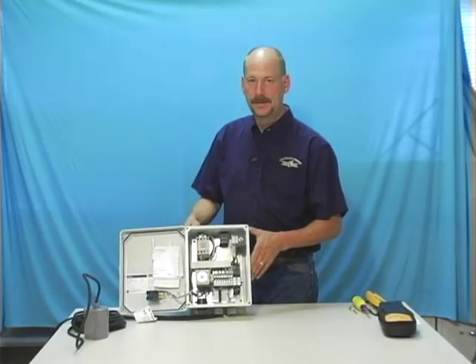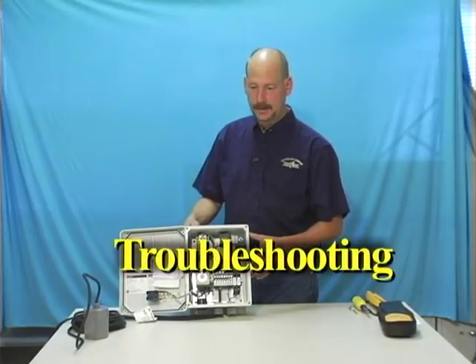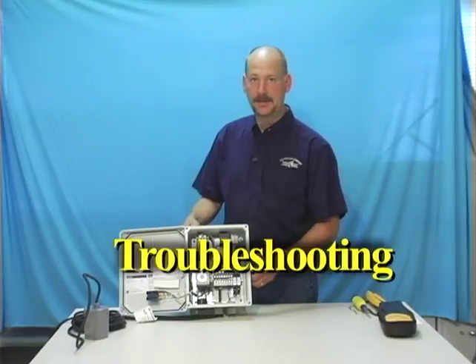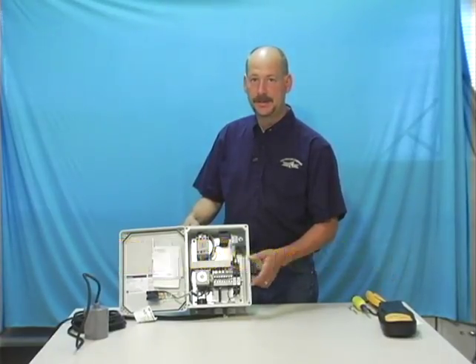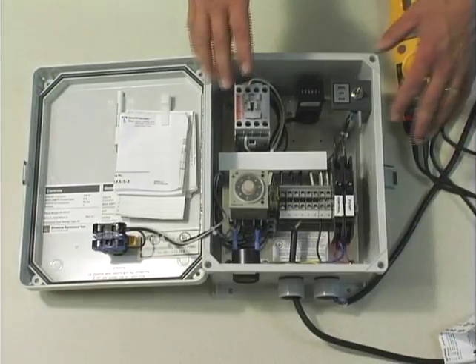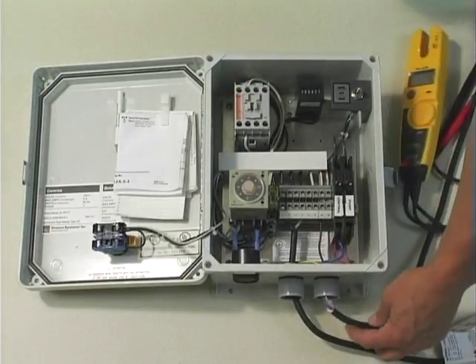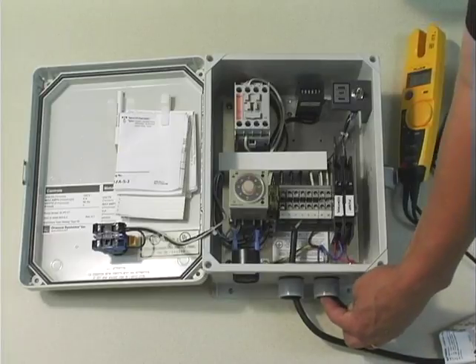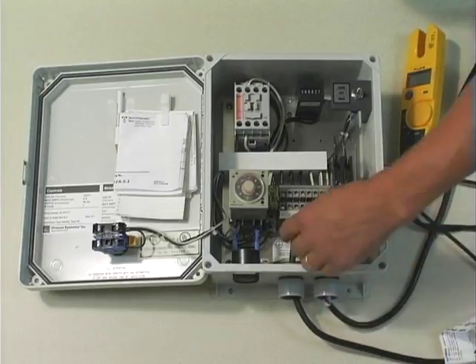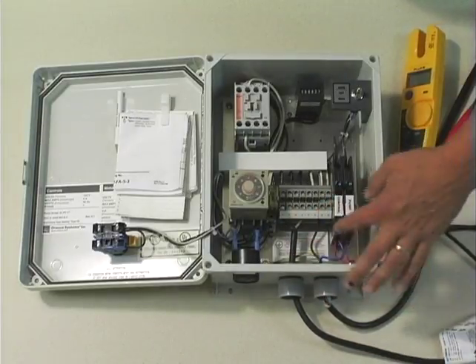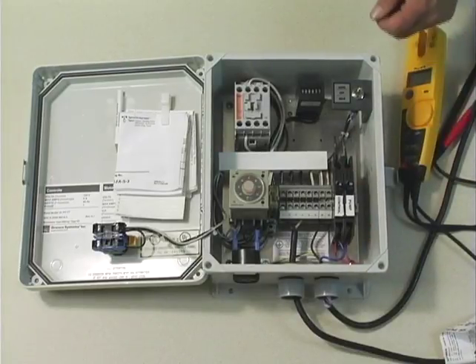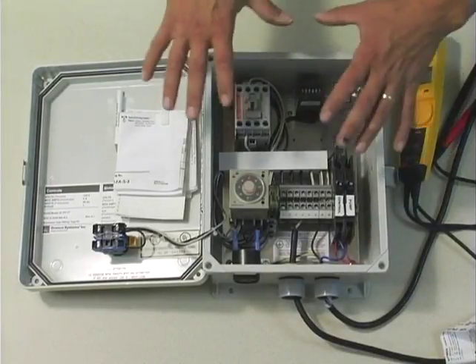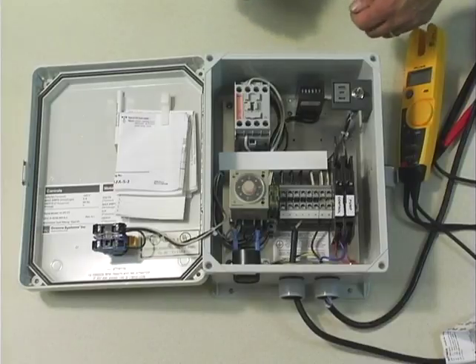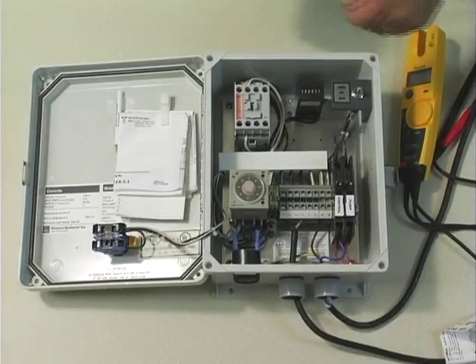Now that you've seen all the different types of control panels that we stock and the different components inside of them, let's get to the actual troubleshooting portion of the class and see if we can't fix what's broken. Okay, with this particular control panel, we've simulated incoming electrical power right here, and we've got a float switch attached. We do have live voltage, it's 120 volts, and we're just going to give you an idea of little components that you should test, where to test them, and how to test them to see if they're functioning.